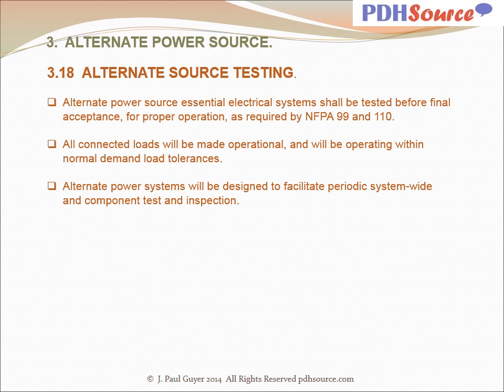Alternate power source essential electrical systems shall be tested before final acceptance for proper operation as required by NFPA 99 and 110. All connected loads will be made operational and will be operating within normal demand load tolerances. Alternate power systems will be designed to facilitate periodic system-wide and component test and inspection.